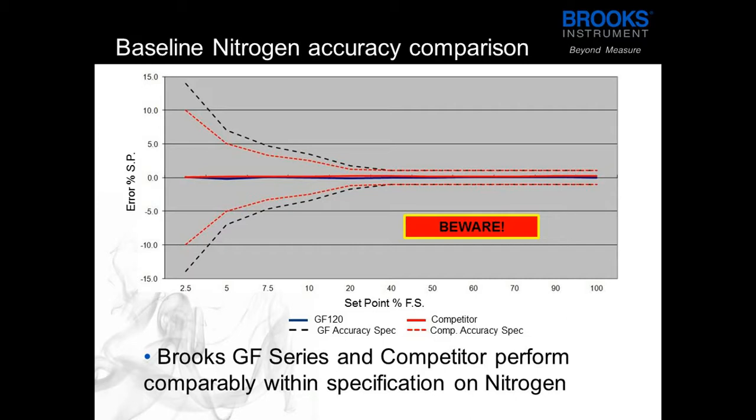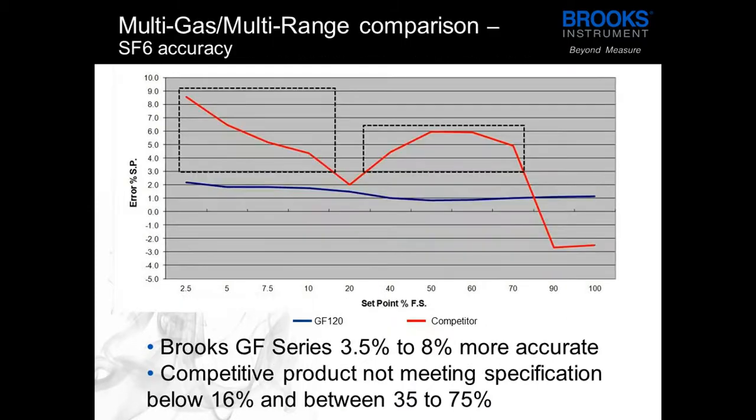It looks like the Brooks device and the competitor device have very similar accuracies but then when the actual process gas is run through, in this case SF6, the results are much more divisive. The competitor device performs poorly due to using only a linear conversion factor while the Brooks device is much more stable and accurate due to the real gas modeling.